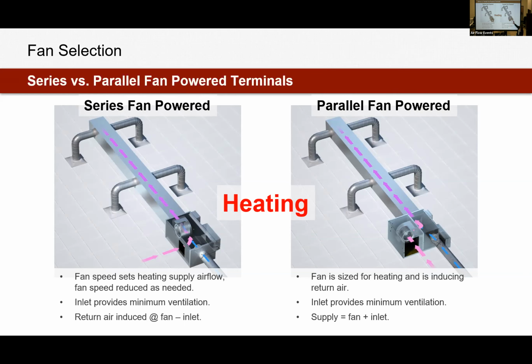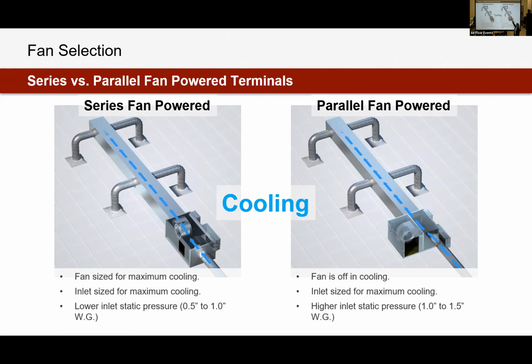Where you're actually losing efficiency on the parallel box is leakage. When we're in cooling and that fan is off, this is a pressurized plenum, and this is almost negatively or neutrally pressurized, so air is going to leak out through this fan opening here. ASHRAE's measured it anywhere from 10 to 15% leakage. So now with ECMs and fan efficiencies kind of out of the picture, leakage is what drops the parallel box down. So I see a lot more series. There are some markets that are parallel and will always be parallel. For example, in the South, Georgia and Florida pretty much only sell parallel boxes because our heating load is little to none for most of the year. Along the coasts, series boxes are the only thing you see.